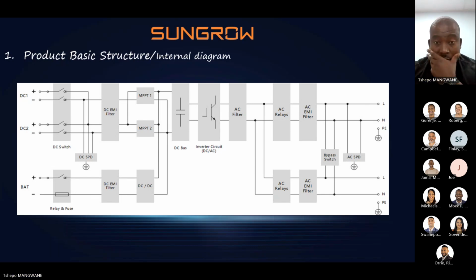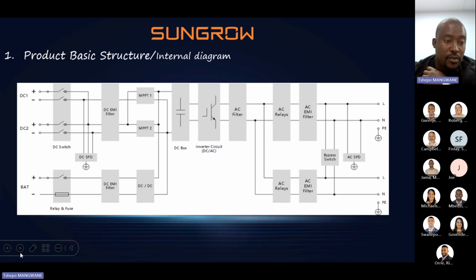Okay, cool. So as I was saying, this is our live terminal, a neutral terminal with ground from the grid side. Should the battery fail in the event of a fault, the inverter will automatically close this bypass switch to supply the non-essential loads, because the inverter will not be working by then if the battery fails. So we have the internal bypass switch as well. Should this fail, the bypass switch will close, then the grid will supply the essential loads as well. Also, we have built-in AC surge protection on the AC side. Sungrow does not void warranty if there is no external AC surge protection installed on the system. We do cover our system, we trust our system.